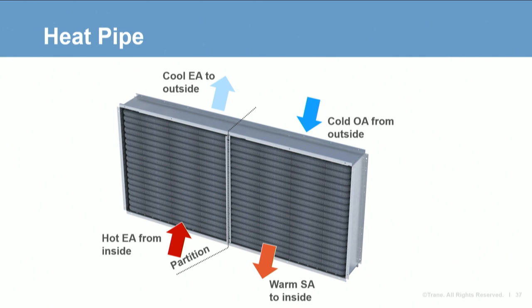The next technology is heat pipes. A heat pipe is like a coil loop but not quite as flexible. The typical configuration requires the airflows to be side by side. Each assembly contains multiple heat pipes, each an independent sealed tube filled with a heat transfer fluid, often refrigerant. A partition divides the heat pipe into separate evaporator and condenser sections. To control heat recovery, units may include bypass dampers to route air around the heat pipe, or valves to restrict the flow of refrigerant.